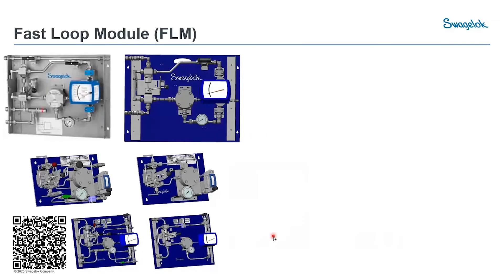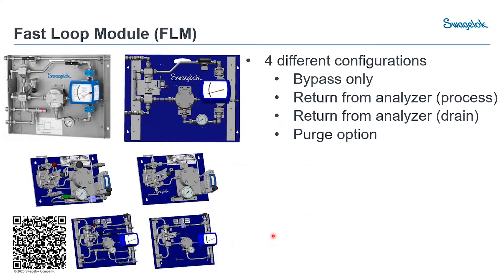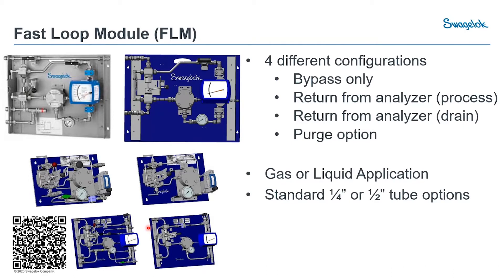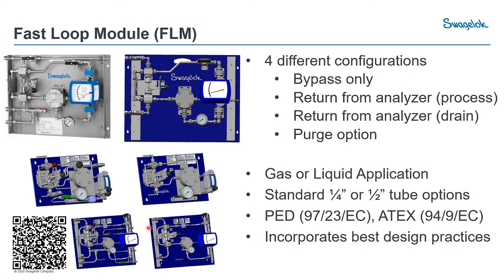Today we'll be talking about the fast loop modules that Swagelok offers. Swagelok offers four different configurations: bypass only, return from analyzer, drain, and a purge option. As you can see in the CAD drawings, they come in multiple configurations for either gas or liquid. The standard tube sizes are quarter inch or half inch, with metric equivalents available. They are PED and ATEX certified and incorporate best design practices.